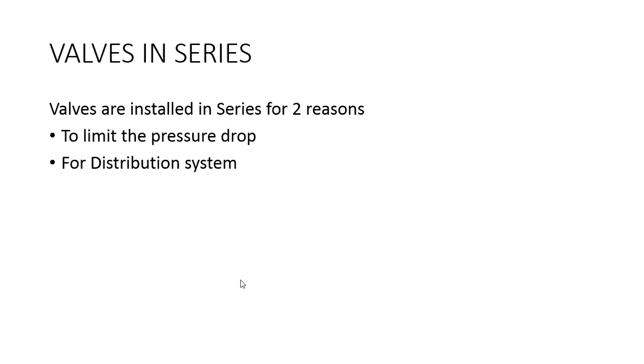Also, consider that spares or maintenance cost of a special trim is very expensive, lead time is very high, and there could be a monopoly for some special trim designs, due to which they are charging a premium. In that case you can have two valves and divide the pressure between the two. When we consider two valves with standard designs, there is a limitation of pressure drop in each valve. One thumb rule is that 2/3 of the pressure drop should be considered for sizing the first valve and the remaining for the second valve. Next is the distribution system, where the first valve is used for pressure reducing while the second is used for controlling the gas flow of the burner.